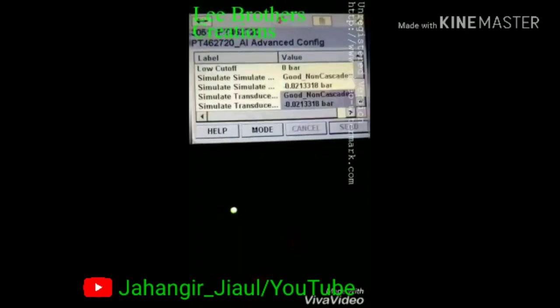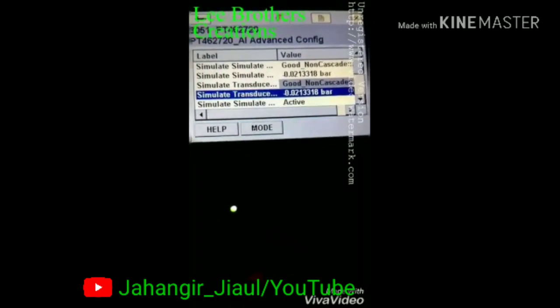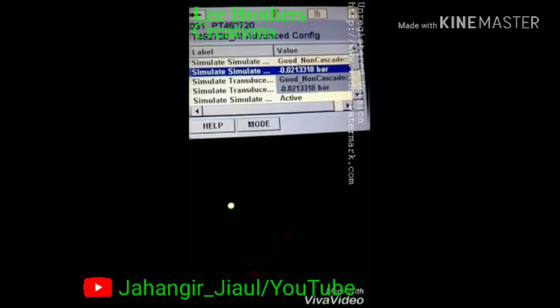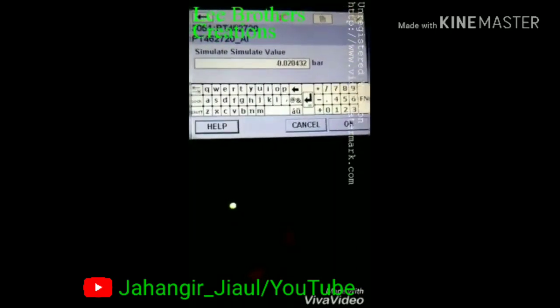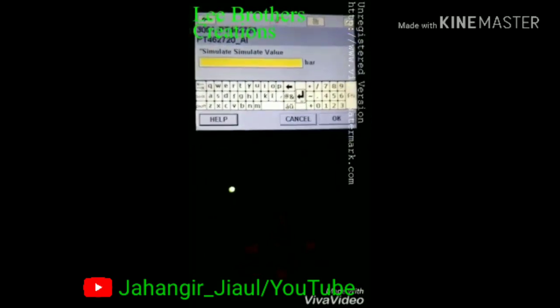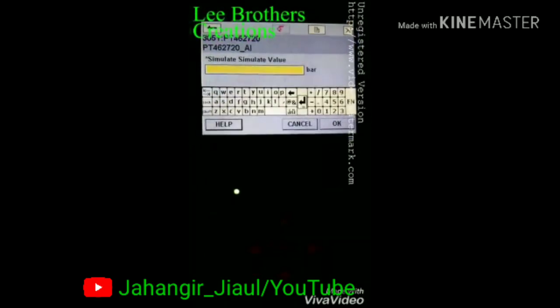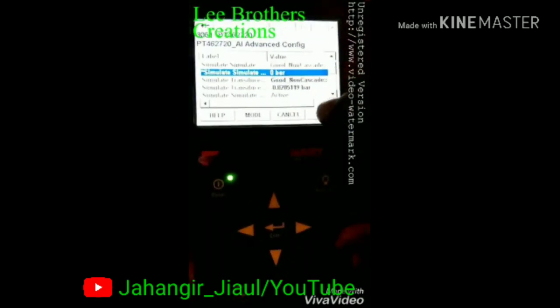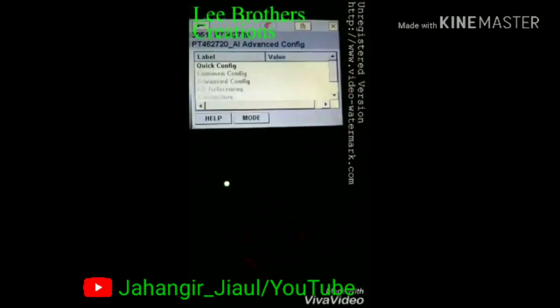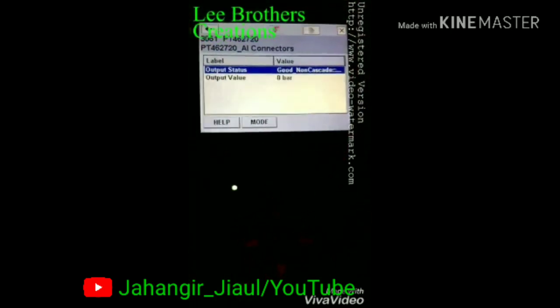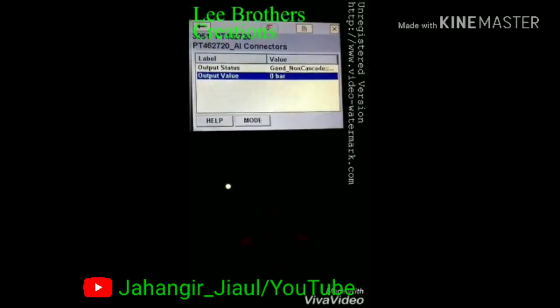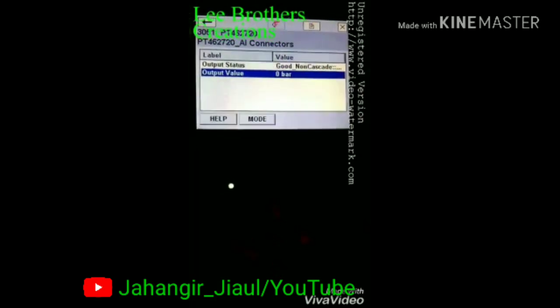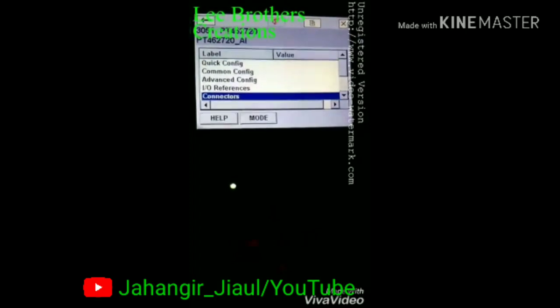Currently simulation is in disable mode. Now I select active and send the active command to activate it. For our loop test, we see that the signal value comes from some value — this is the actual value of this pipe. To set the simulation value, I enter 0 and click OK. Here 0 is automatically sent to the DCS control room, and it is now showing 0 in the DCS control room.